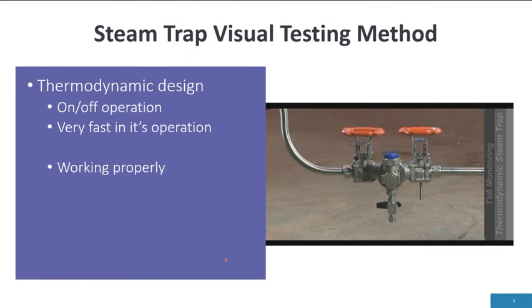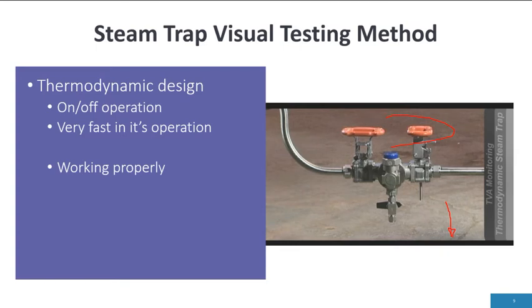As you're seeing, visual testing is very simple. Here is a thermodynamic design — another one of the different steam trap designs we have. It is on-off, but the thermodynamic trap is very fast in its operation. As the handle is activated, you'll see the distinct on-off operation. This trap is working properly — in the off cycle, there is no steam or condensate coming out of it, and when it comes to the cycle mode, you'll see the discharge.